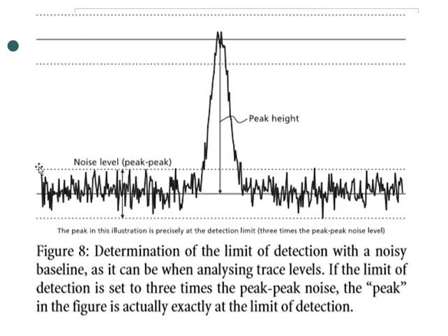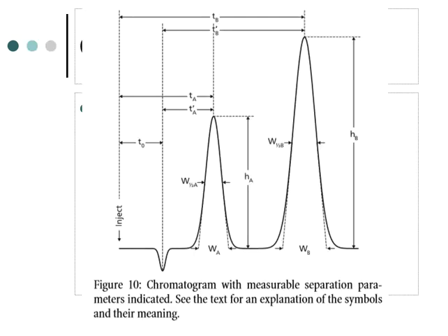Nothing really over that amount, and if so, it's not going to be that much. And then whatever that height is from the bottom or the baseline, we want 3 times that height. You can see here in this diagram, it is 3 times higher than the actual baseline at the very bottom. That's what we would call limit of detection, and that's how we would determine how low we can go with our instrument before we begin to get any problems at all.